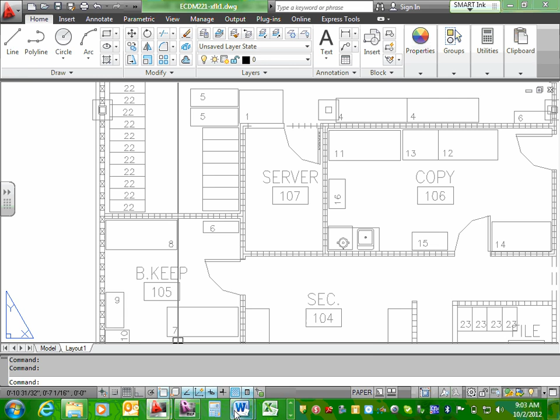Electrical service, 2.2. We want a 208/120, 3-phase, 4-wire service. You have to size it, find out how large it needs to be amp-wise—again, it needs to be sized to handle a 5,000 square foot addition. It kind of lists what we want fed out of the main distribution panel. We want TVSS surge suppression on the main service.